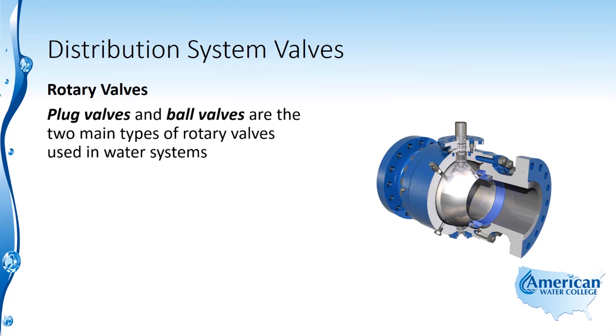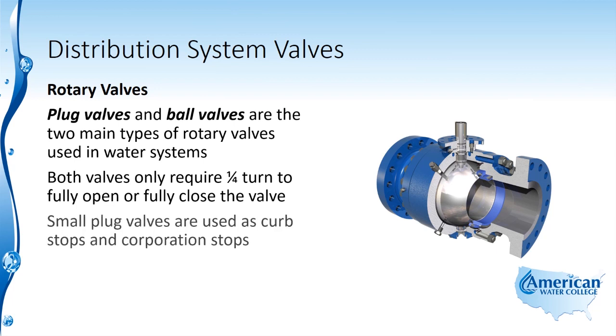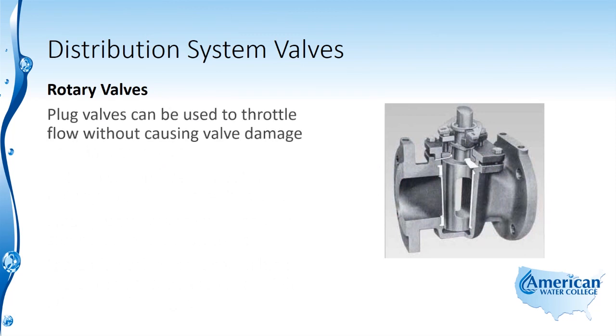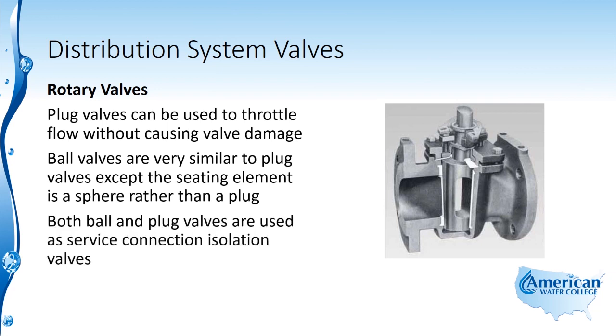Plug valves and ball valves are the two main types of rotary valves used in water systems. Both valves require only one quarter turn to fully open or fully close the valve. Small plug valves are used as curb stops and corporation stops, while large plug valves are used in high pressure applications such as high lift pump discharges. Plug valves can be used to throttle flow without causing valve damage. Ball valves are very similar to plug valves except the seating element is a sphere rather than a plug. Both ball and plug valves are used as service connection isolation valves.